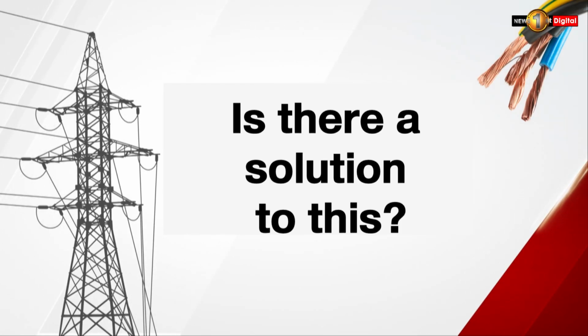Is there a solution to this? We discussed this issue towards the end of last year at the Ceylon Electricity Board. There are several measures we can take, but they require time. The main solution is to install battery systems, known as grid-scale battery storage systems, at grid substations. This would allow us to maintain stability by storing excess power during low demand and using it during high demand. If we can keep the system at around 1000 megawatts, we can ensure stability by sending excess power to the batteries.